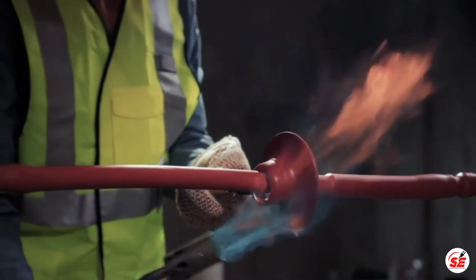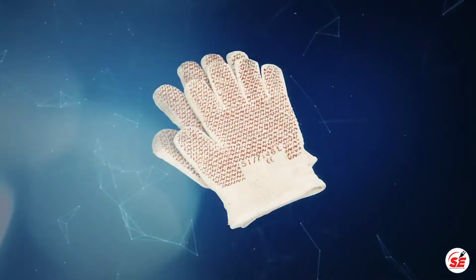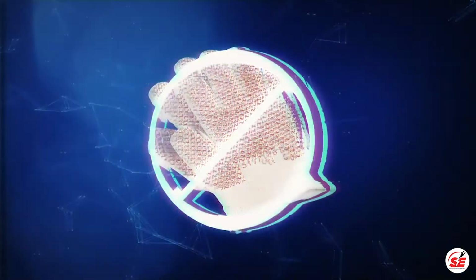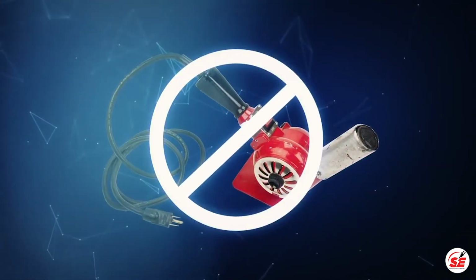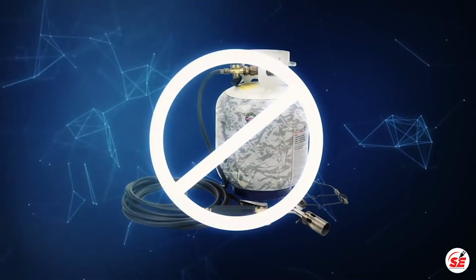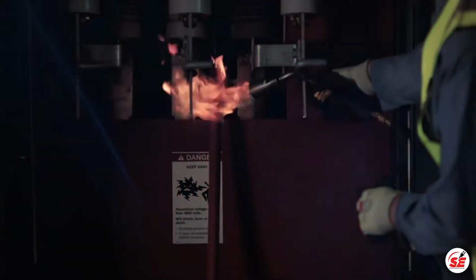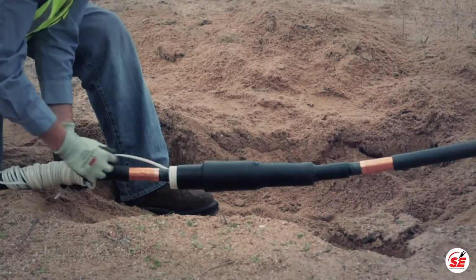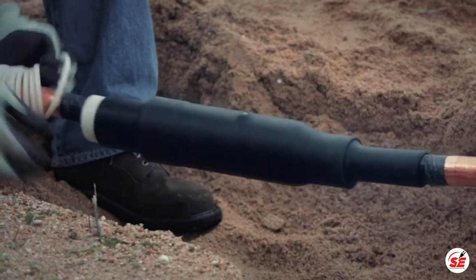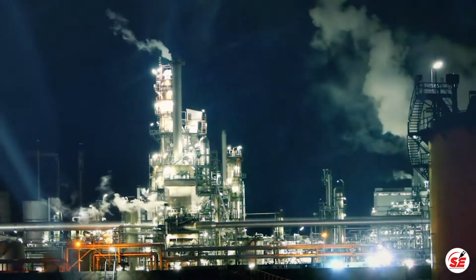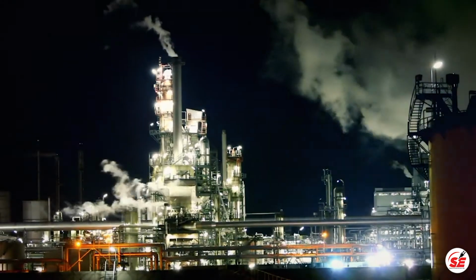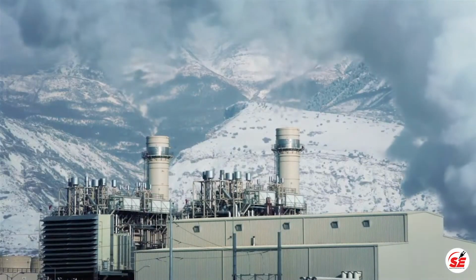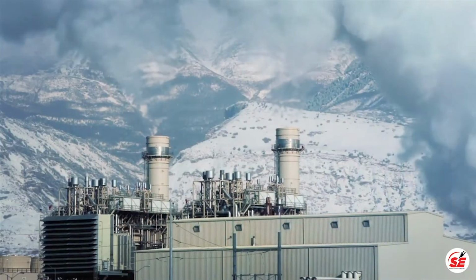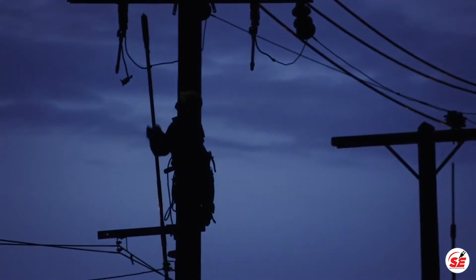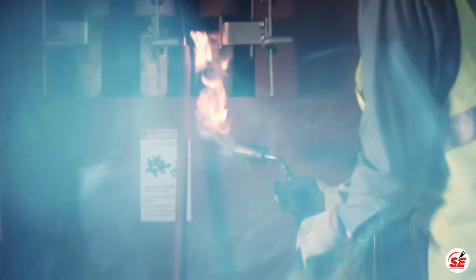No special tools or heat sources are needed with cold shrink, which can be a real advantage when installing in tight places, like switchgear and ditches, or in inclement weather conditions. Also, it doesn't carry the same safety concerns as heat shrink, which sometimes requires shutting down a facility before an installation to minimize the danger of explosions from combustible gases.